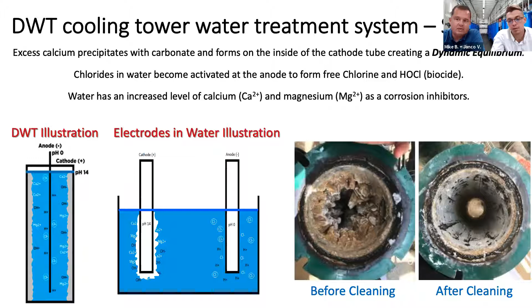In this slide, you can see some of the calcium and magnesium, and this is from drinking water. We're pulling these minerals that would form scale inside the reactors or inside process water systems, your heat exchangers, your cooling towers, your process piping, and putting it in a place where we can service and maintain it. The benefit of this is quite remarkable because the heat transfer surfaces are optimized, and the water sanitization is much more effective. This has been proven time and time again versus traditional chemical water treatment. It's better, faster, and cheaper than the traditional process.